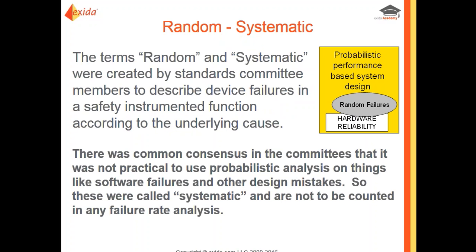Some background on the random versus systematic debate: these terms were created by standards committee members to describe device failures in a safety instrumented function according to some underlying cause. There was a common consensus in the committees that it was not practical to use probabilistic analysis on things such as software or design mistakes, so these were all considered systematic and therefore not counted in any failure rate analysis.